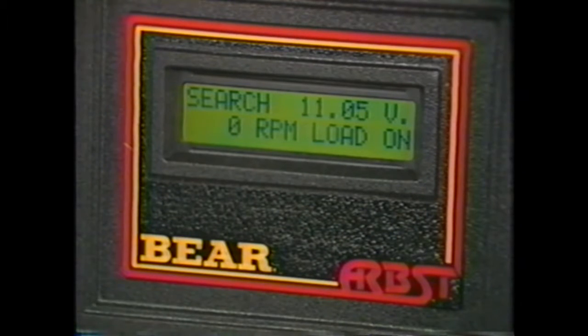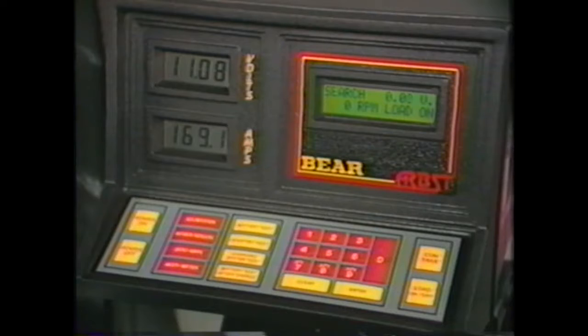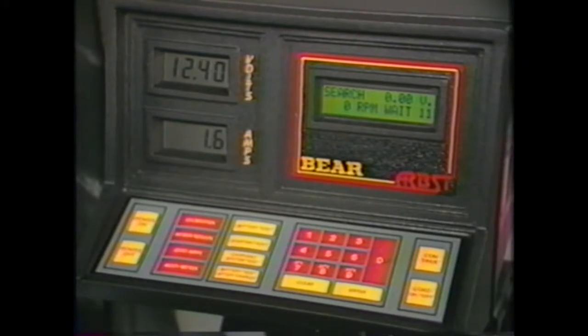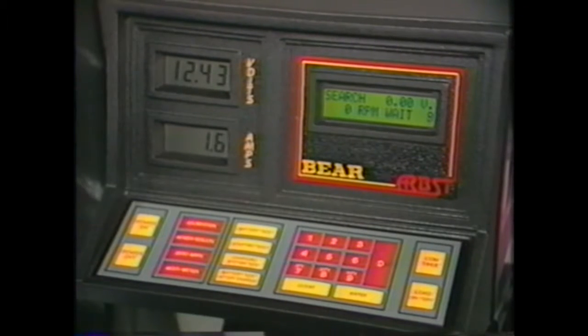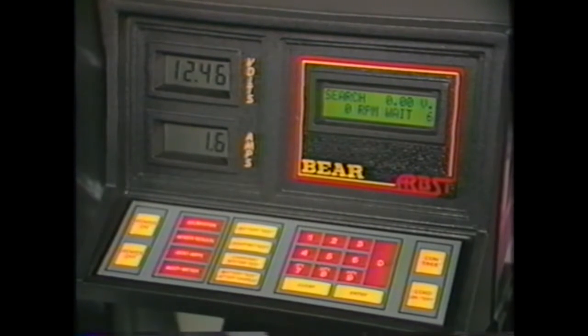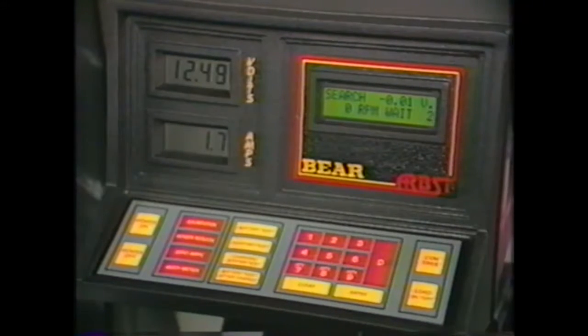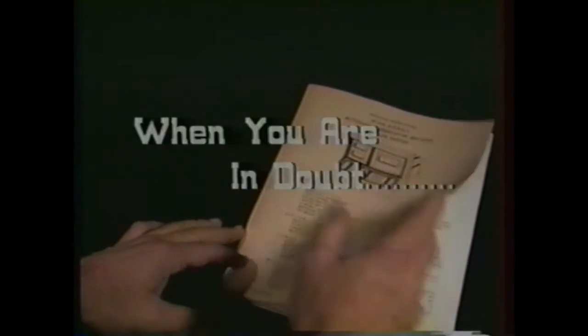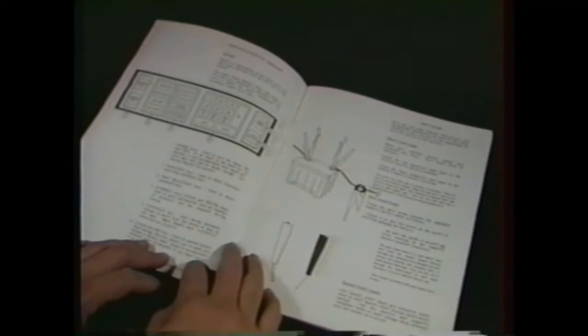The load will automatically remain on for 15 seconds, or you can shut the load off before 15 seconds are up by pressing the load key a second time. After the load is shut off, there is an automatic cool-down period for the same length of time that the load was on. During this period, the display says, "Wait," and counts down to 0. This concludes the operational portion of the video. Refer to the written operating instructions included with your tester if you need additional information.